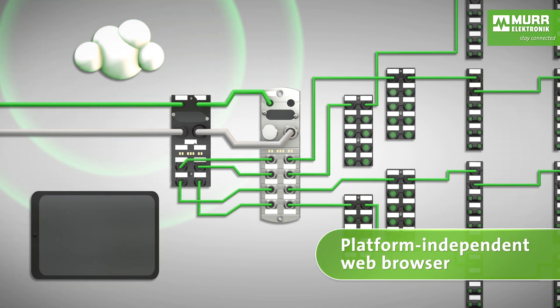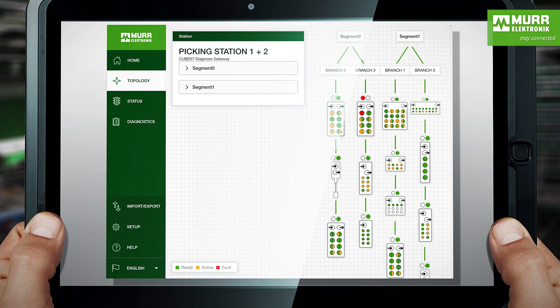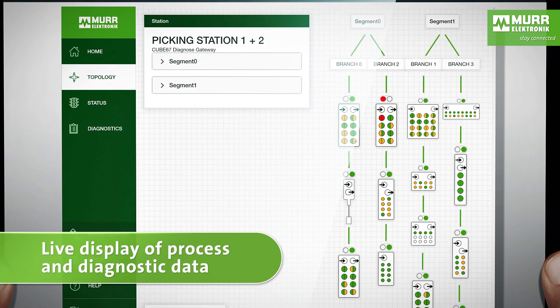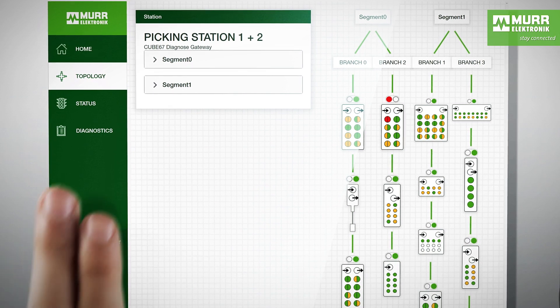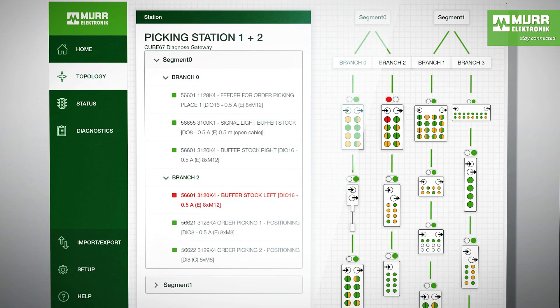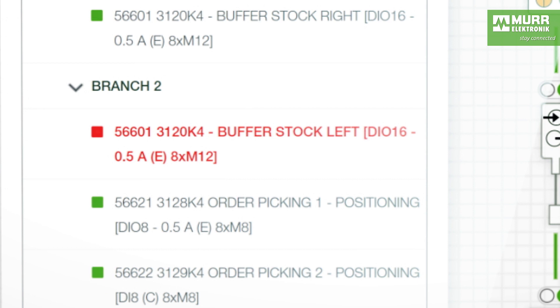The current topology is shown live and visually represented on numerous devices. If an error occurs, this is shown not only on the I/O module, but also in the browser of any device connected via the Ethernet interface. A simple text import allows the gateway to know the machine areas down to the individual sensors and actuators by the name you provide during assembly.